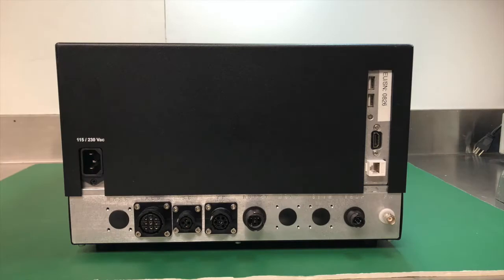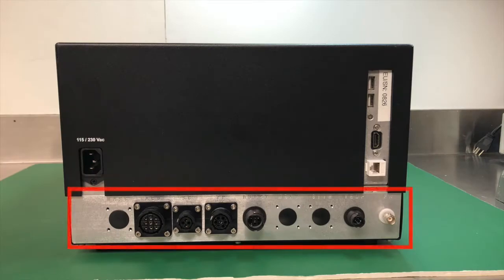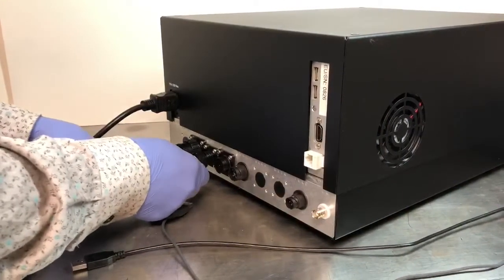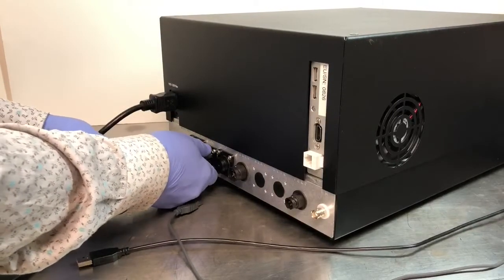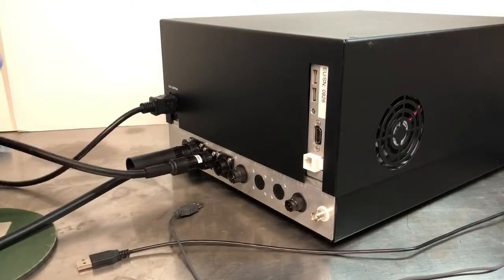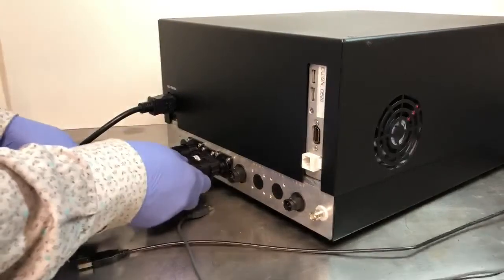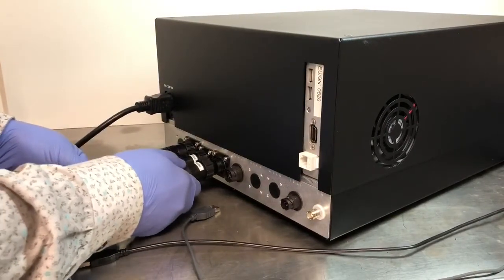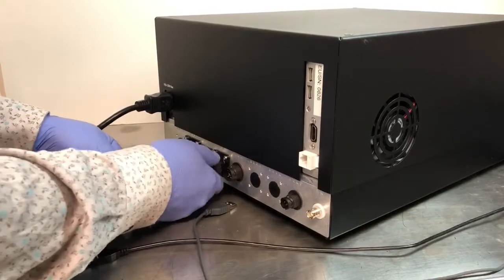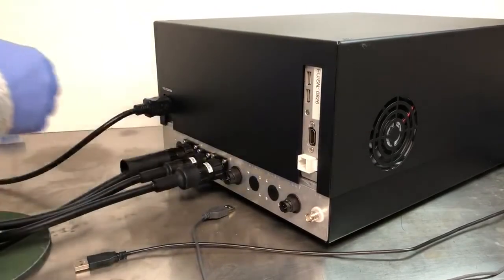At the bottom of the rear of the electronics box are a series of ports for the sensors of the DT-1202. The amount of ports here varies depending on the options purchased with the instrument. All sensors can be plugged in by hand, requiring no additional tools. Be sure, when plugging in the sensor cables, to properly align the plug with the port in order to avoid cross-threading. The ring on the plug is turned clockwise until it locks into position. You should feel it click into place when the plug is fully connected.